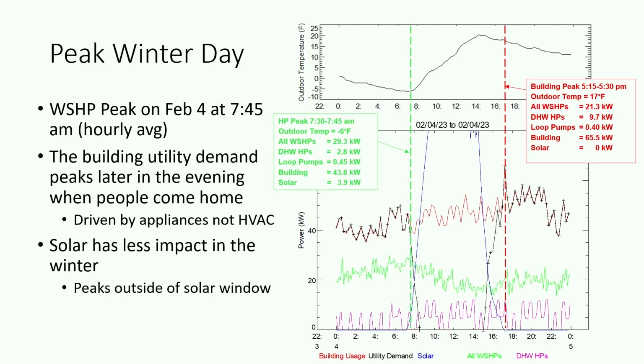So peak use. Here is a peak winter day, and it was February, and it got down to -6 early in the morning, at 7:30 in the morning. So a little bit of a busy graph. Here's the outdoor air temperature. Here is total building power. You can't see this well, but I show the output from the solar array. I didn't talk about the fact this building has a solar array. It has 240 some odd kW of solar. And it had a big contribution to the building, but I'm going to show it didn't have much impact.